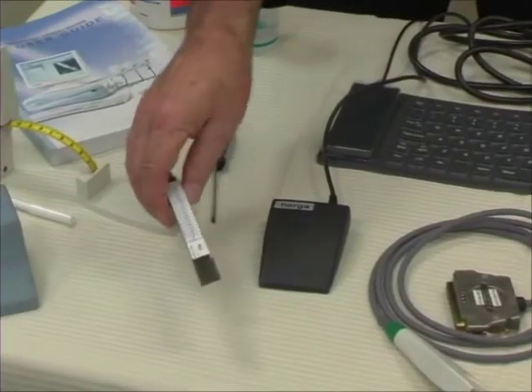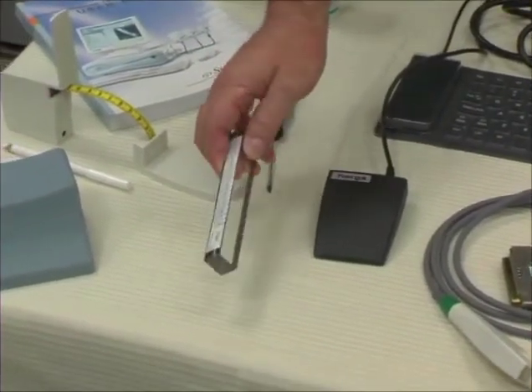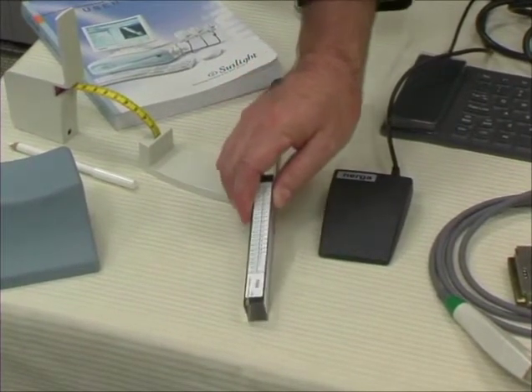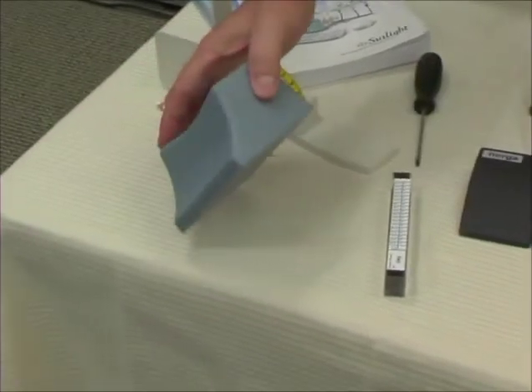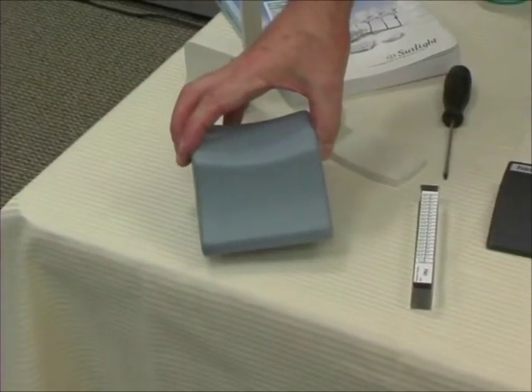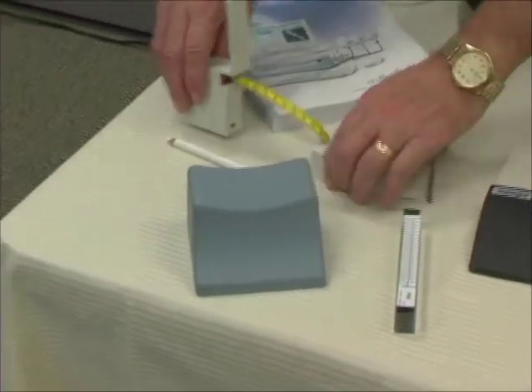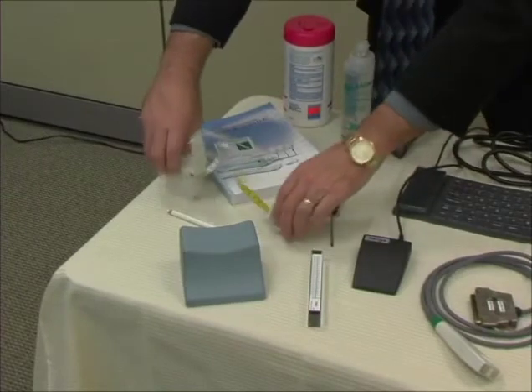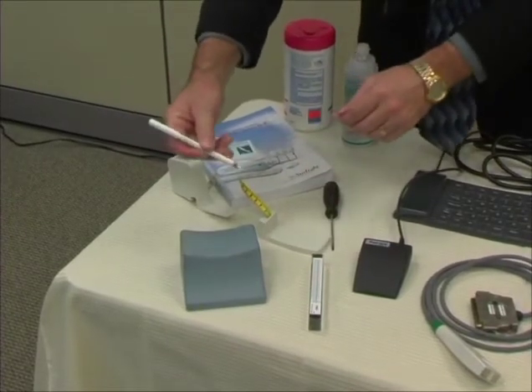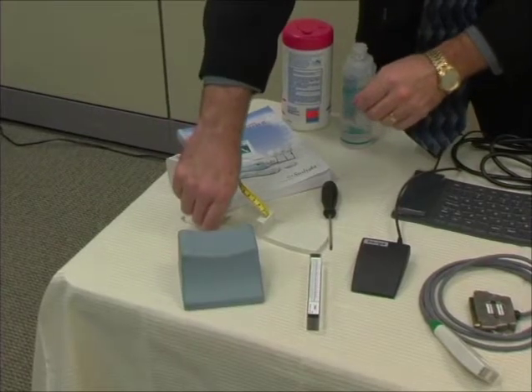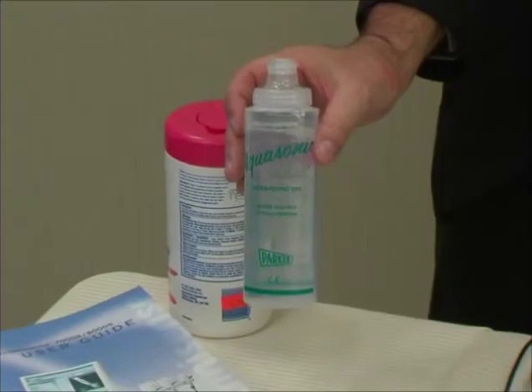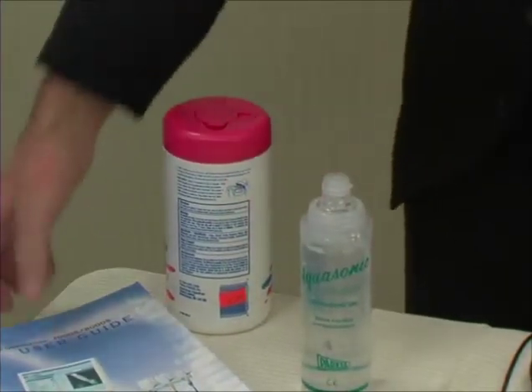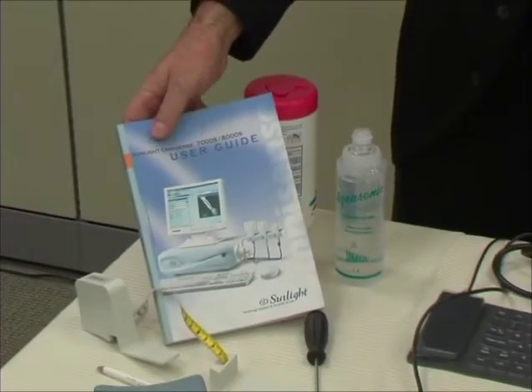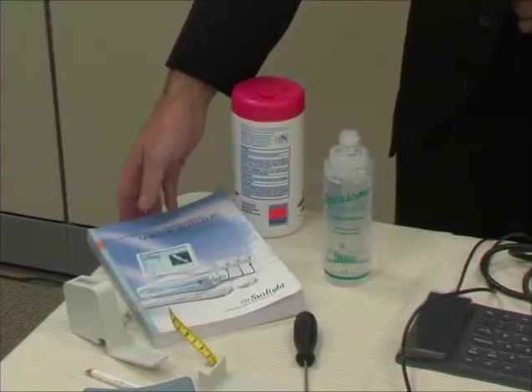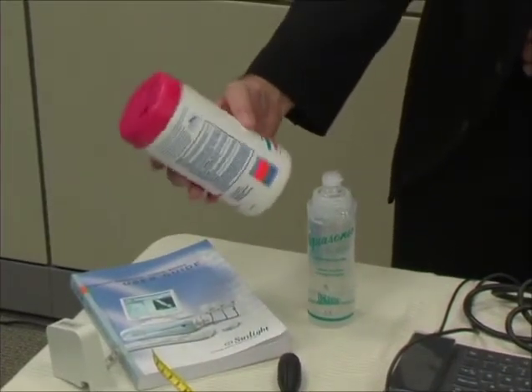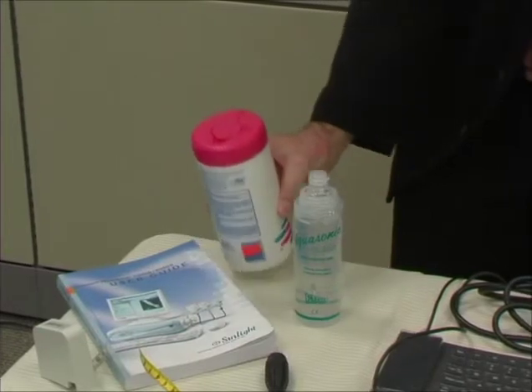We have a phantom, and this is an interesting device. As you can see, it's clear, and it's for system quality verification. We'll talk more about the phantom in just a moment. We also have limb positioning fixtures to help put the arm at rest in the correct position. We have measuring gauges and a marking pencil because we are going to have to measure the length of the arm from the elbow to the tip of the finger. We have a bottle of ultrasound gel to help the probe glide smoothly along the skin. We have a user's manual, which of course is always handy. And finally, towelettes for cleaning. These need to be non-alcoholic, so anything that would be appropriate for a baby's bottom, for instance, would be appropriate for cleaning the probes and for cleaning the skin. So something like a baby wipe, for instance.